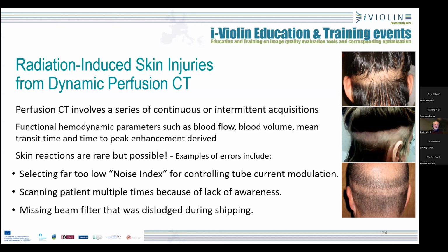So it shows what can occur if you don't understand all the settings. Scanning patients multiple times because of this lack of awareness resulted in these effects. But you can also get the effects, it's been reported, when a beam filter was missing or dislodged. If there hadn't been a proper acceptance and testing system in place, then that would have given similar dose levels.